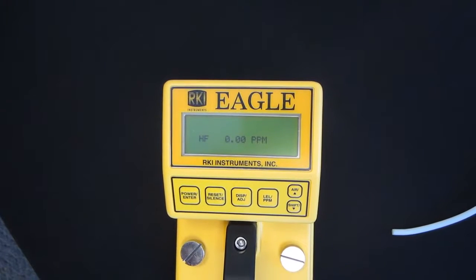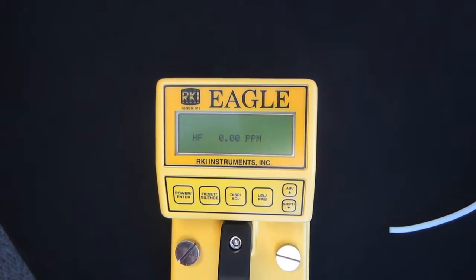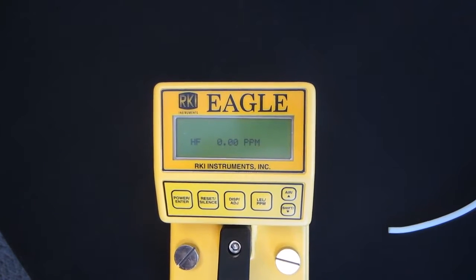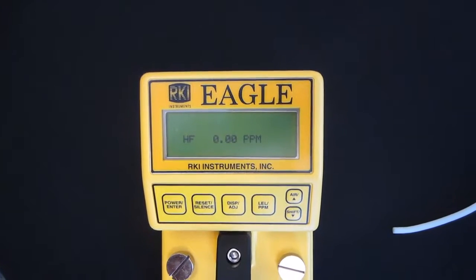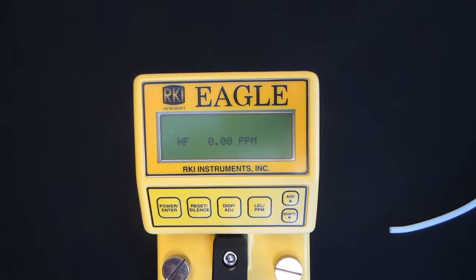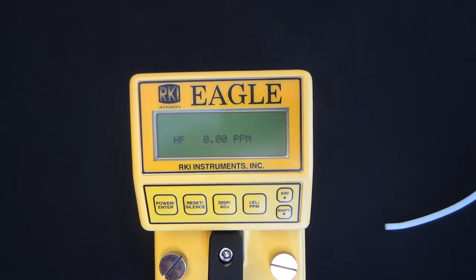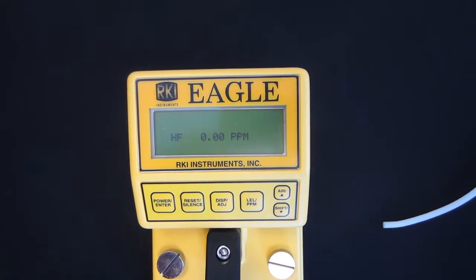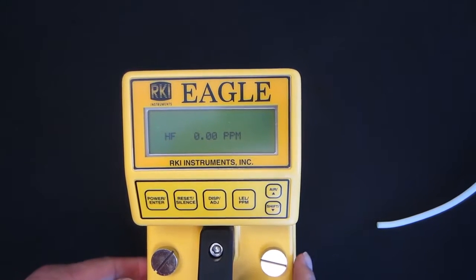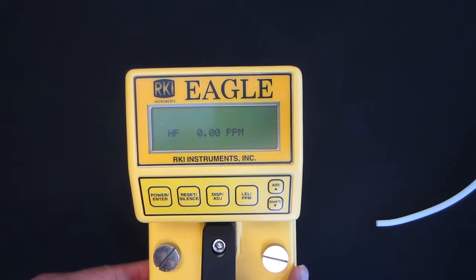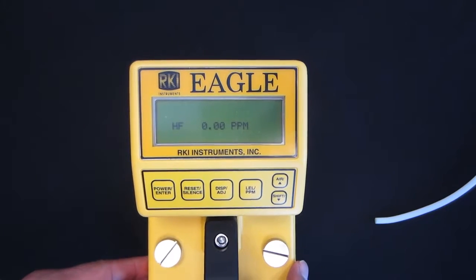We're here to calibrate the Eagle with an HF sensor using chlorine gas. HF gas is not available in a disposable cylinder, so we actually can use chlorine as a substitute gas. However, in doing so, we have to take note of a conversion factor for chlorine to HF.